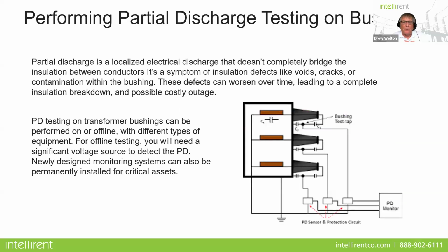Another test that is getting more and more popular is looking for partial discharge. Partial discharge is a localized electrical discharge that doesn't completely bridge the insulation between conductors. It's a symptom of insulation defects like voids, cracks, or contamination. We do PD testing on cables all the time to look at the health of the insulation. We do it on transformer windings, on motors, on generators. PD is becoming a very, very popular test in terms of getting that first indication of insulation problems.